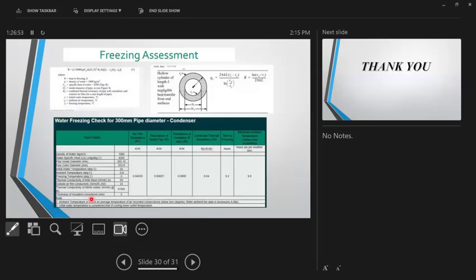This is one slide which probably is not applicable for your region, but good to know kind of thing. Freezing assessment. The places where, say, in Eastern Europe or Northern Europe, where the chilled water or condenser water systems are in a place where the temperature can go sub-zero, -10, -20, -30. If you really don't give attention to anti-freezing systems, you can really have a problem that your pipe can burst. What happens is when the water becomes ice, its volume increases, and the pipe or system can burst.